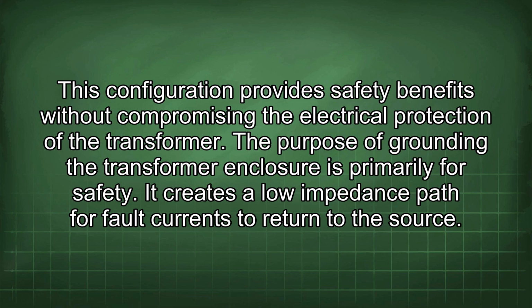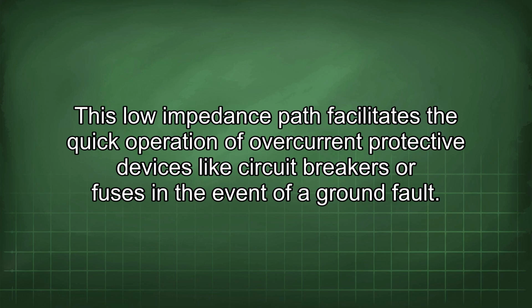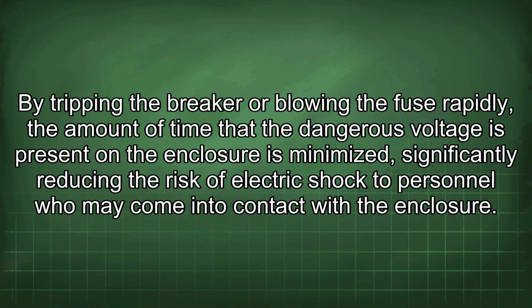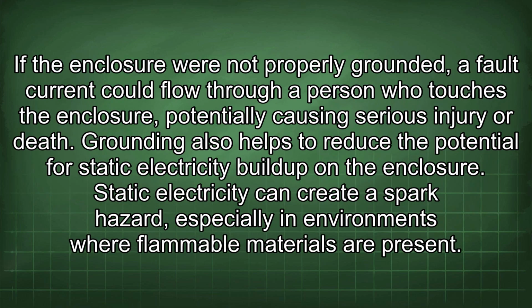The purpose of grounding the transformer enclosure is primarily for safety. It creates a low impedance path for fault currents to return to the source. This low impedance path facilitates the quick operation of overcurrent protective devices like circuit breakers or fuses in the event of a ground fault. By tripping the breaker or blowing the fuse rapidly, the amount of time that the dangerous voltage is present on the enclosure is minimized, significantly reducing the risk of electric shock to personnel who may come into contact with the enclosure. If the enclosure were not properly grounded, a fault current could flow through a person who touches the enclosure, potentially causing serious injury or death.